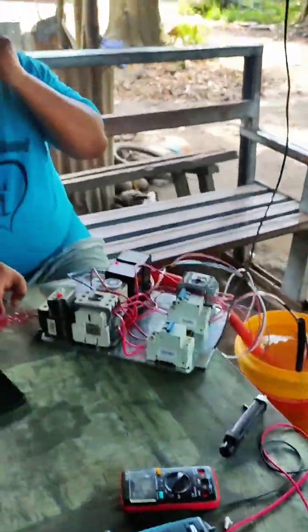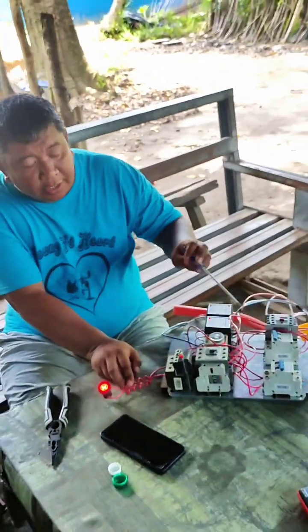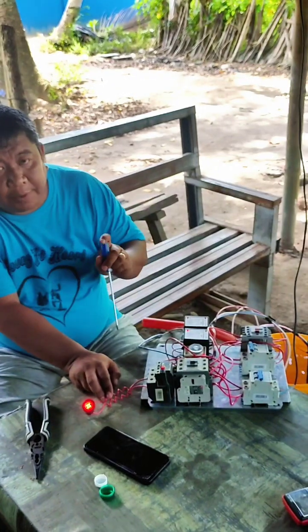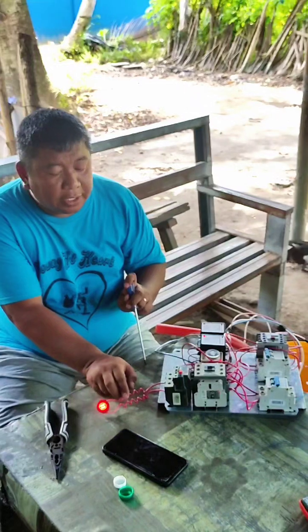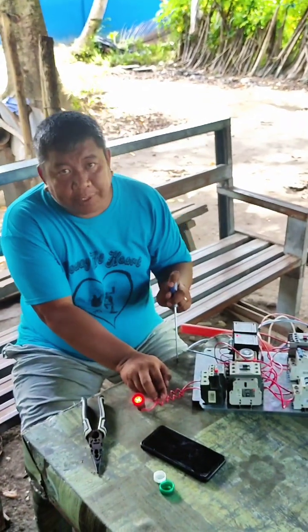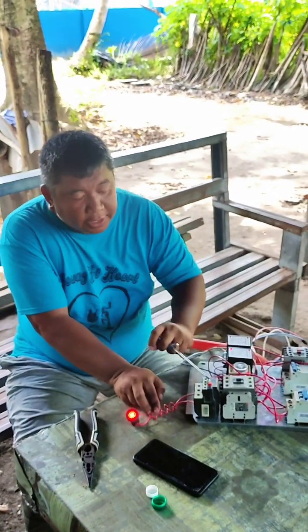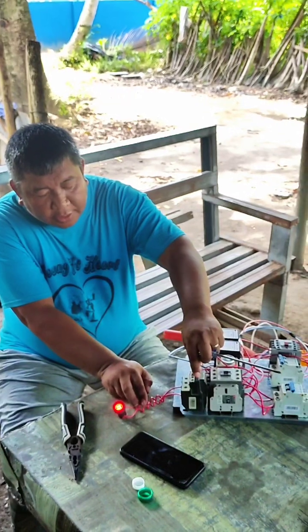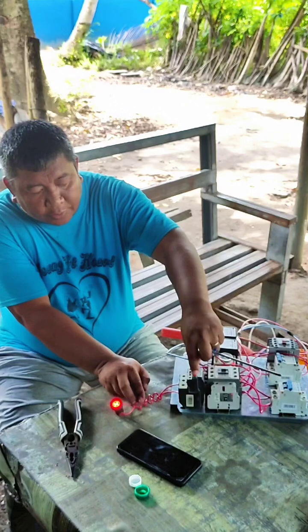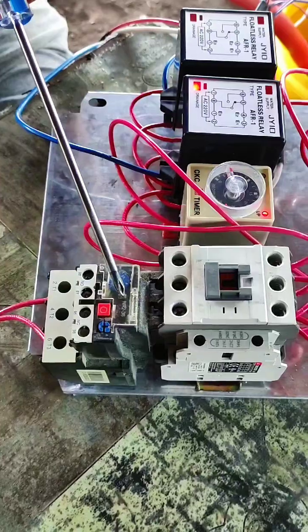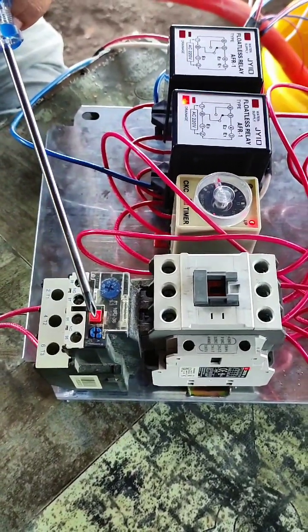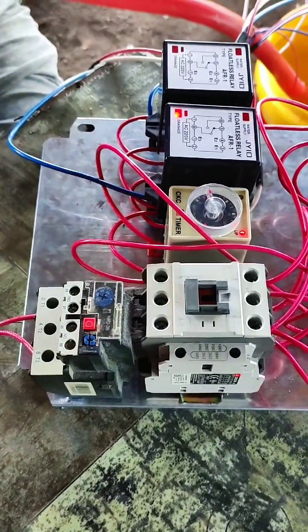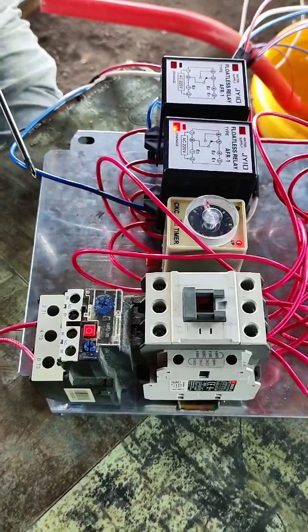Let's demonstrate first the manual. This is on manual mode, right? Let's demonstrate the overload relay. Say for example there's a trip on power. We need only 32 amperes and it overloads to maybe 40. We manually trip it, and the motor protection would engage. There's an ampere setting here. So this is the overload relay. If you trip this one, it would disengage. For example, if there's a short circuit, this overload relay would disengage too. This is the reset button. You just reset if it engages. We first remove the short, and then we can reset it.